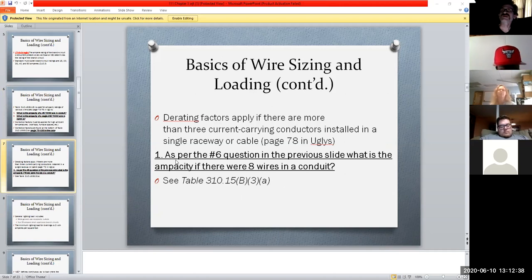And next week we'll have an exercise where we'll go through and try to size our own circuit. But we do have derating factors that we can apply with the 3 current carrying conductors installed in a single raceway. And it's pretty common. We'll have the hot, the neutral, and a ground wire generally traveling to any given circuit. We may have more in a conduit, but very typically this is what we have coming to an outlet, right? Is our three wires.